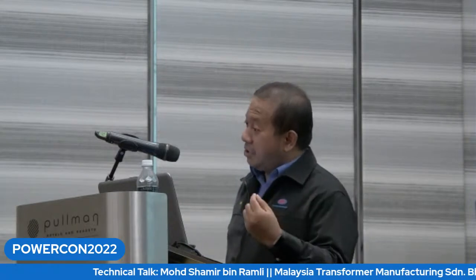Thank you. In terms of the ester oil, you are right again. When we talk with our parent company about the strategy of having ester oil in the transformer, we are cautious about replacing one-to-one, because as you rightly said, the specification of transformers may be different. The way they conduct the cooling of the transformer is different these days, and with the increased viscosity of ester oil, that may impact the cooling of the transformer.